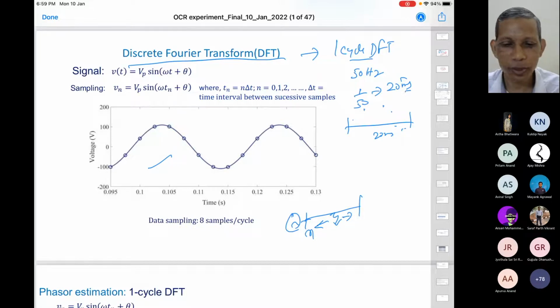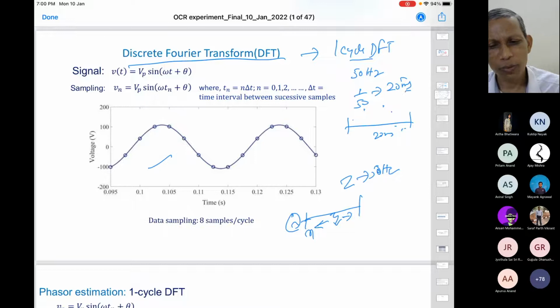My point is that if your design philosophy is based on Z, on the 50 Hertz component, impedance omega L, then you have to go with 50 Hertz. If your design philosophy is based on harmonic components, as I said in the transformer case, then you have to think from the harmonics perspective also. But what you say is correct, the harmonics and other components will be responsible for possible damage. Our purpose here is to identify whether the fault is internal, external, or there is no fault. To have that discrimination function, we are using certain features. You can use fundamental 50 Hertz, you can use harmonics, and there are enormous varieties; what we are using in this case is the fundamental. Is it okay?